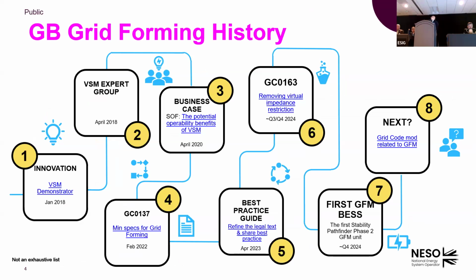So our journey for grid forming really started around 2013. When we initially did some studies, we asked: if we keep on increasing the penetration level of IBRs, at which point might we run into system problems? So we did some studies with academia, continuing to increase the penetration level. And we started to find out that when the IBR penetration level increased to 60 to 70%, we were running into stability issues.